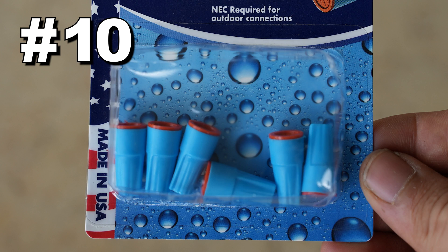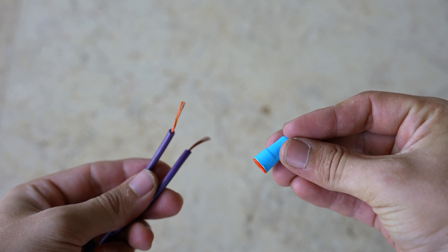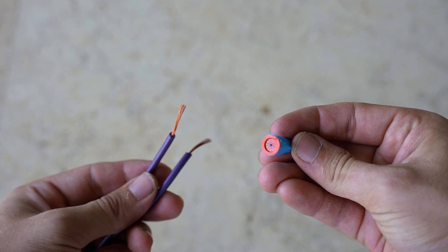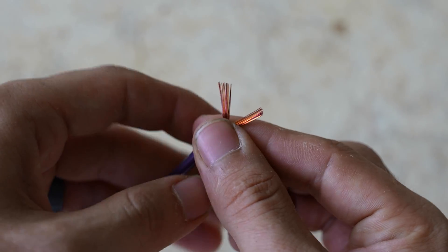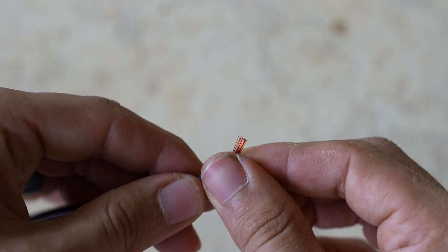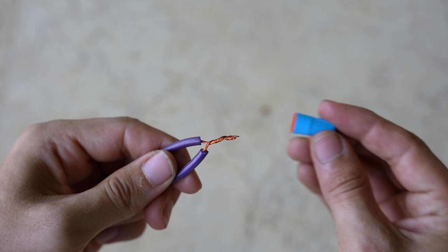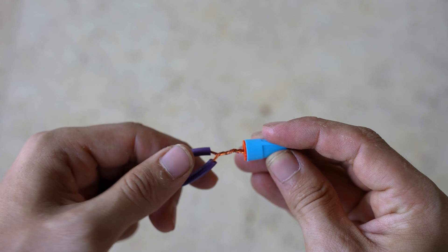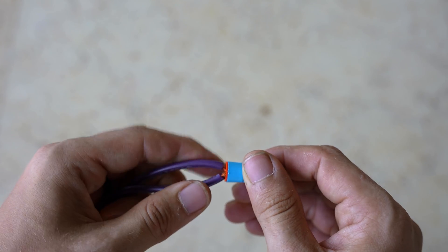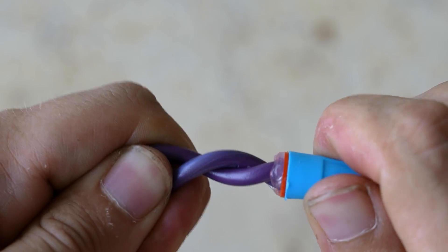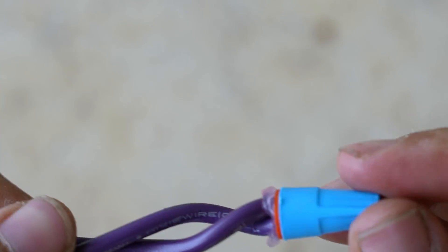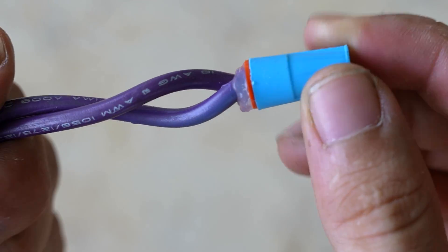Number ten is waterproof connectors. These are basically wire nuts that are filled with silicone. With this one, I do like to pre-twist my wires as it makes it easier to push them into the wire nut and get it started. In my opinion, this right here is the best waterproof connector, since the bare wires are encased in silicone and some of it also gets squeezed outside of the wire nut, preventing any water from getting in.